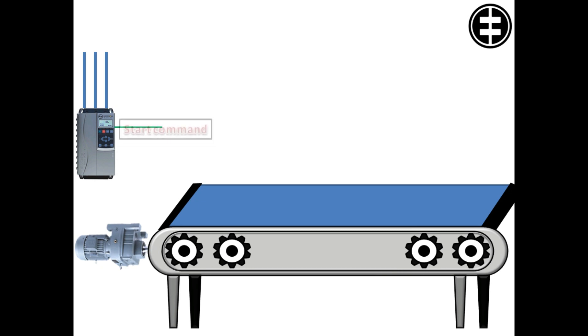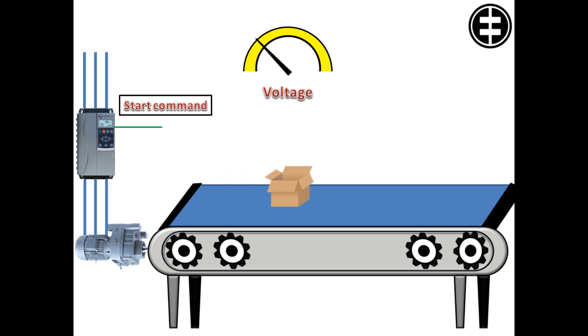A soft starter can control the motor to have a slower start by limiting the voltage to the motor, so the generated torque is reduced too. This creates an increase in slip, causing the motor to slowly build up to full torque over a set time and reducing the amount of inrush current as a result.